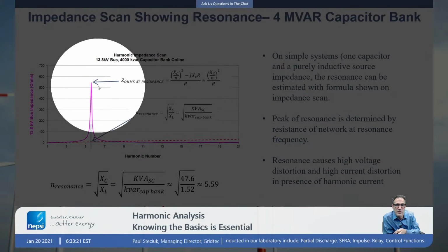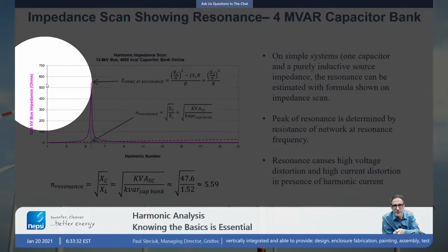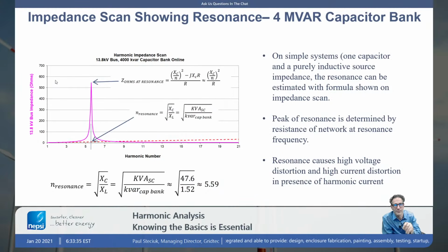So at resonance, the peak of the impedance curve really defines the possibility of what voltage distortion you can get. The interesting thing to note here is we're at a value of about 600. So even 1 amp of current injection at that harmonic would result in close to 600 volts. 600 volts line to neutral. So these are single phase calculations. It's a line to neutral voltage value. So 600 volts on a 13.8 system, which normally would be 7,960 volts line to neutral, would represent a very high voltage distortion for just 1 amp of current injection.